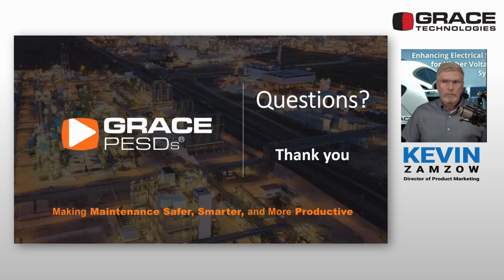Will the DC version have the indicator lights as well, Kevin? Yes, the DC version of the 2-wire and 3-wire will have the voltage indicator lights. The line load version for use with combiner boxes, the 4-wire, will not have the indicator lights.